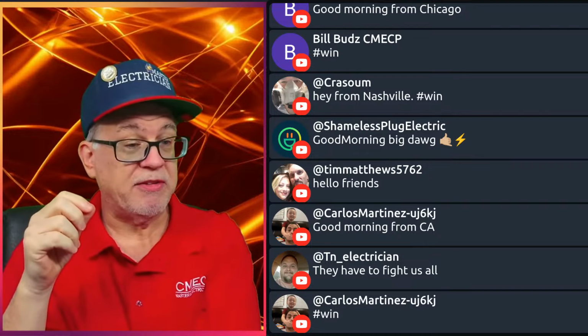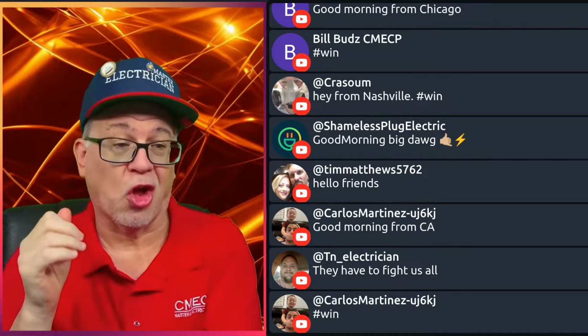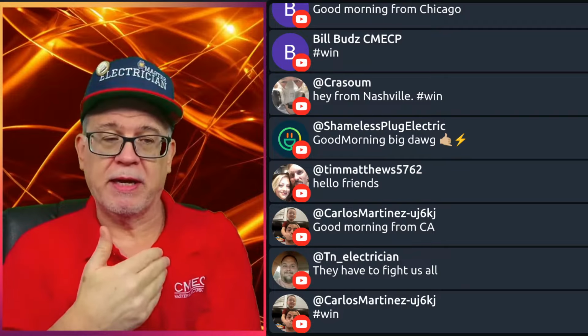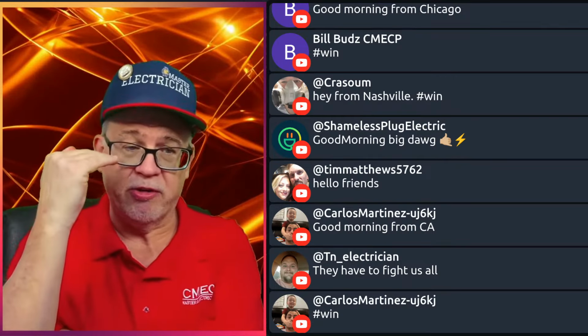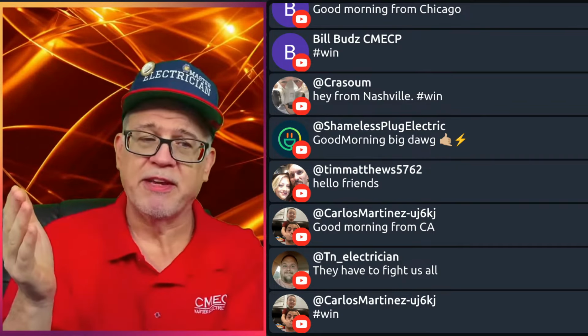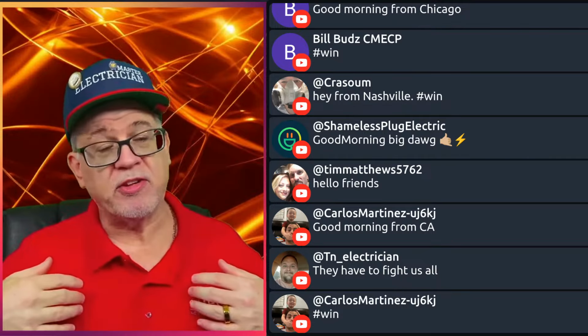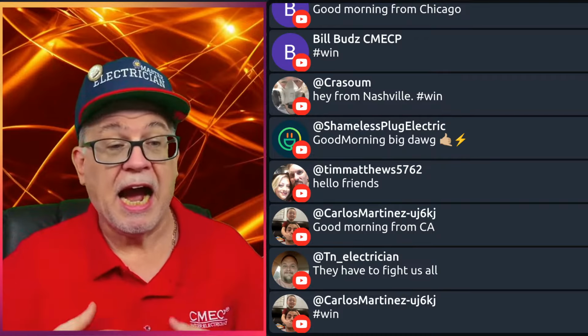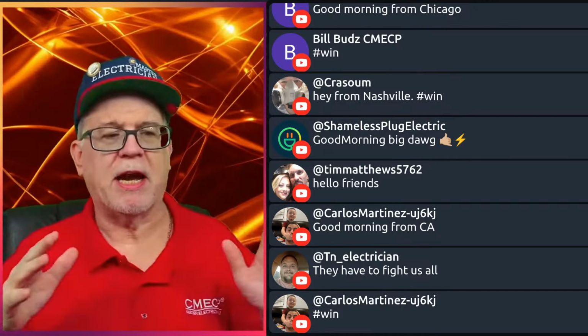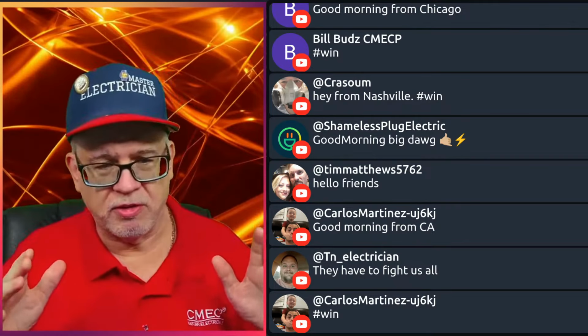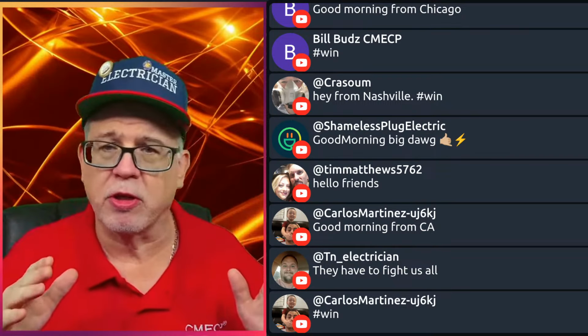Now, if I'm doing this basement and adding something special, like a sauna or a hot tub, then you've got to reevaluate the size of the service to make sure that you have enough headroom on it. We do have a coffee hour where we talked about that. Then you're going to look and see whether you still have some additional capacity to be able to do that. Now, I'll tell you how I do it. I make life simple. If I'm looking to see whether a service has additional capacity, I personally take it as a mission to redo the calculation myself. So I'll go through and gather all the appliances and everything and do it like it's a fresh load calculation.